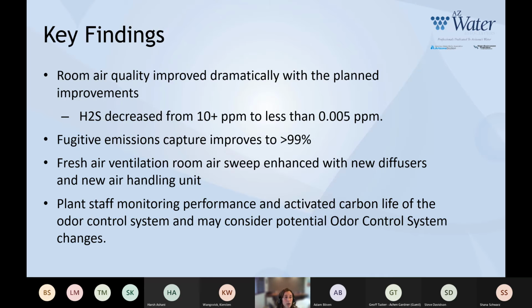So our key findings were that room air quality improved dramatically. You could see the H2S decreased from greater than 10 parts per million to less than 0.005 parts per million, which I think satisfies the goal of providing safe working conditions. We captured fugitive emissions at greater than 99%. We noticed the difference with the fresh air ventilation, with the new diffusers and the new air handling unit. And as Adam just chimed in and I had mentioned, I know that they were monitoring the performance of the carbon life, and that led to the ultimate decision to change the treatment entirely.